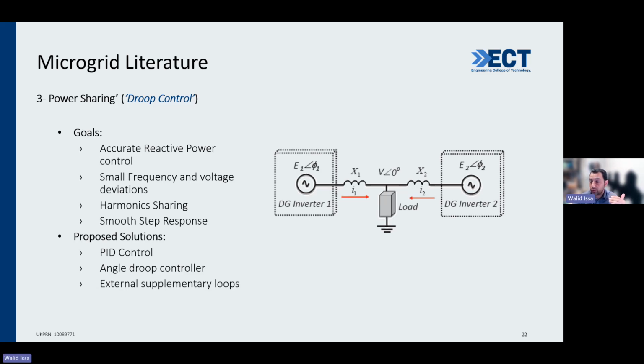We need small frequency and voltage deviation. Again, when you push power into the grid or into the bus, that frequency will deviate up or down. That deviation, for example, in island mode, has to be restored somewhere. And also harmonic sharing. For example, if we have customers, unfortunately, they use equipment that generates harmonics. How do we make the inverters also share the harmonics? We can't make one inverter produce harmonics that maybe stress the components and cause a problem. We want to share the harmonics, not just the power.